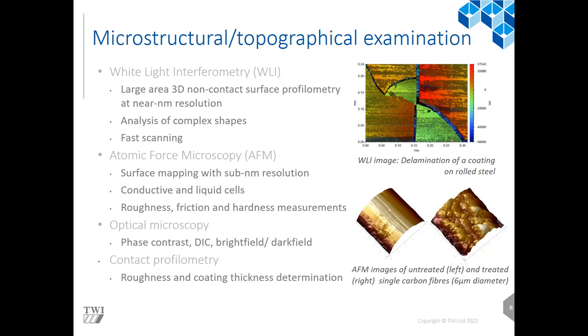For higher levels of resolution, we use our AFM — atomic force microscopy — which allows surface mapping, measurement of conductive surfaces and liquid cells, and gives us roughness values, friction values, and hardness values. The surface preparation required is greater than for white light interferometry, so we recommend starting with the white light interferometer and moving to AFM only if necessary, unless the client has good reason to go directly to AFM.